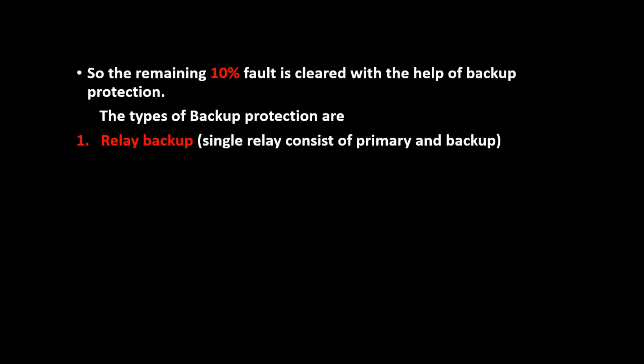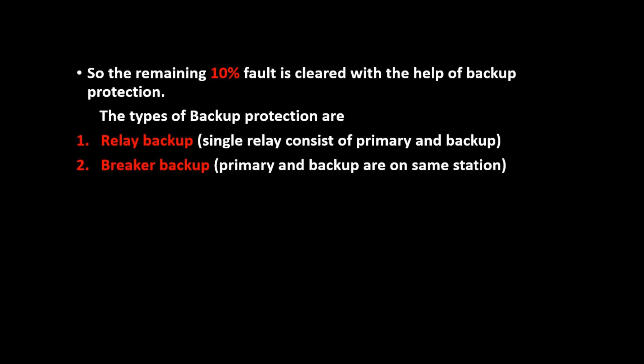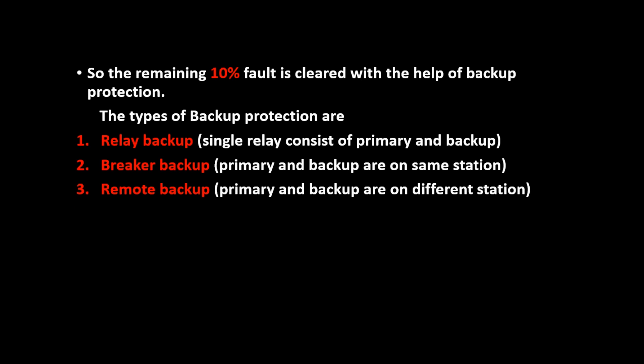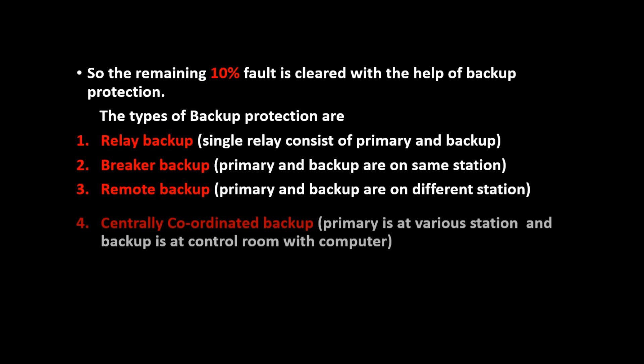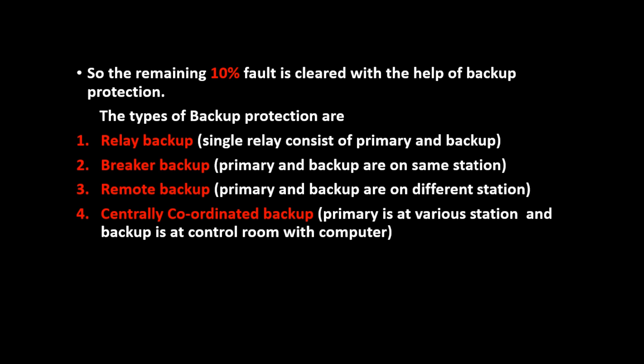The types of backup protection are: Relay backup, where a single relay consists of both primary and backup. Breaker backup, where primary and backup are on the same station. Remote backup, where primary and backup are on different stations. Centrally coordinated backup, where primary is at various stations and backup is at a control room with a computer.